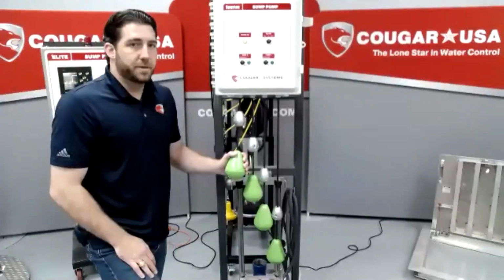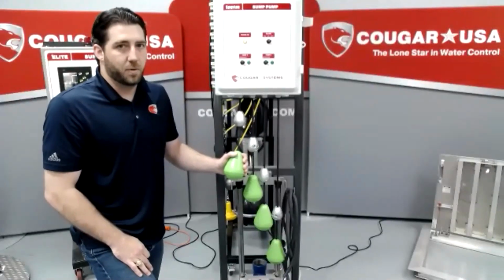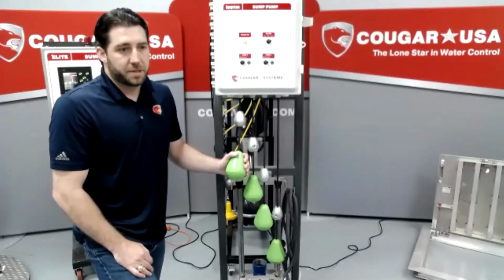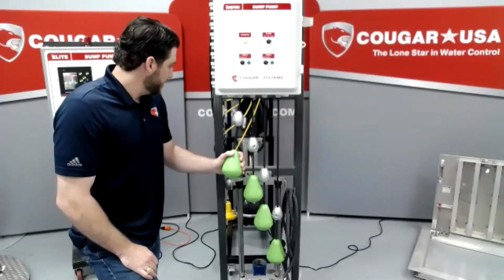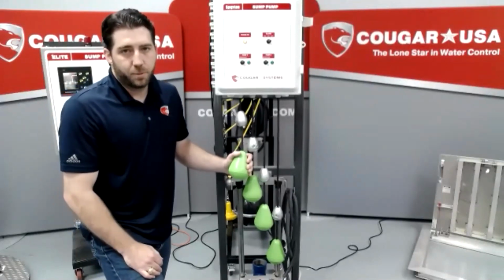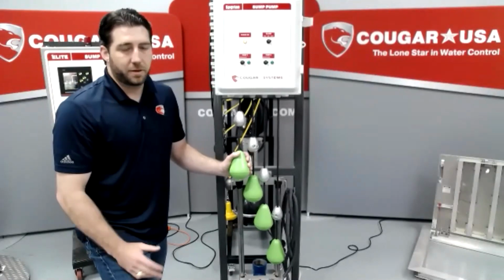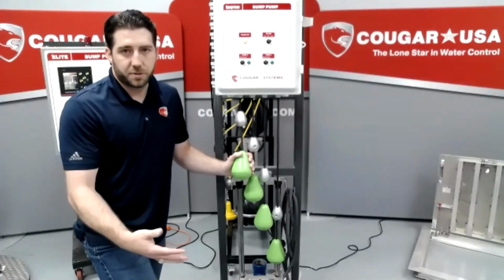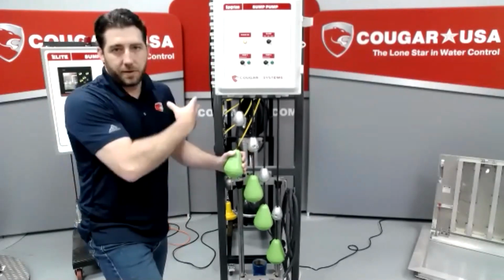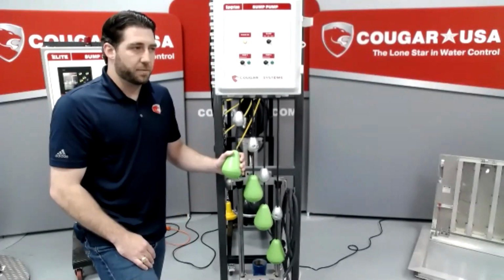That's probably going to be limited by the wiring more so than anything else. I think the Grundfos pumps are standard with a 50-foot cable. The floats, we can go up to like 150-foot cable, but you could always do a junction box at the pit and then run additional cabling away from there.